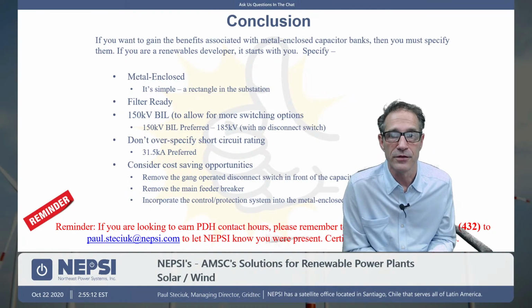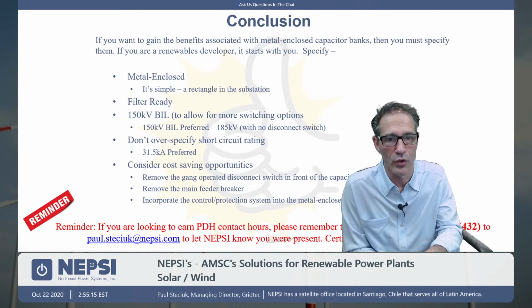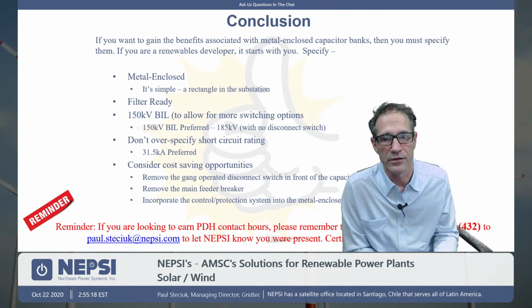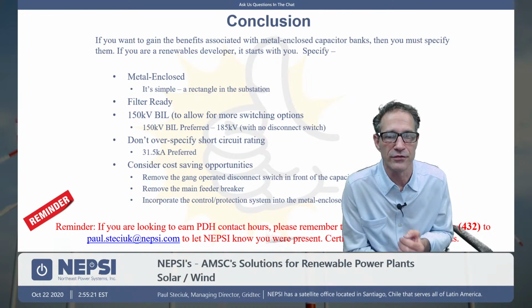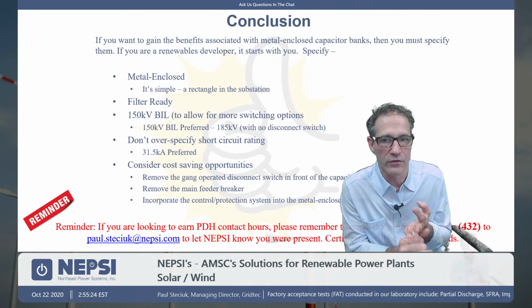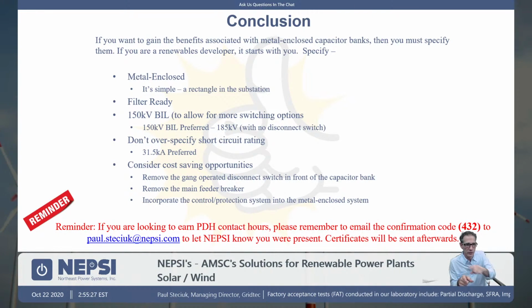And consider the cost savings. When you're evaluating our equipment, consider the cost savings. Remove the gang operated disconnect switch in front of the equipment. Remove the feeder breaker in front. Because we have breakers in our gear, you're going to pass that collector bus basically into our gear, and you're just adding 2 more additional breakers or 3 breakers, whatever number of stages you have, and those breakers will provide the short circuit protection, so you have a savings there. And then think about incorporating the control and protection system into our system. If you do that, it eliminates all of the site work and all the testing on site, because it's going to leave our factory in 1 or 2 pieces and it'll be ready to go.